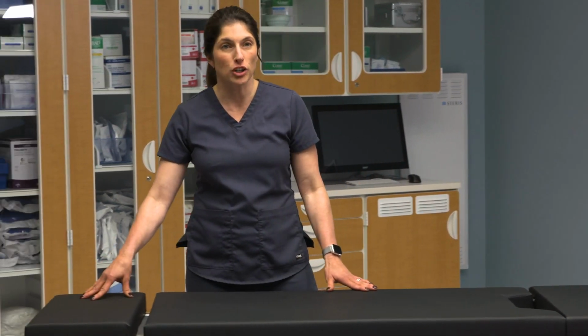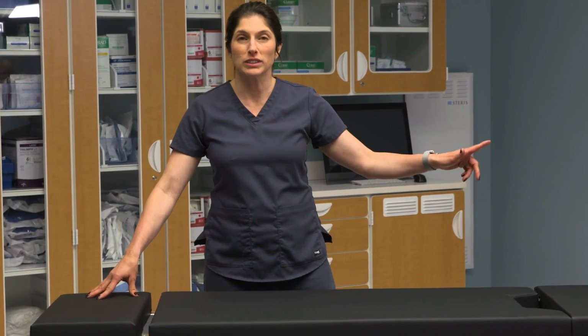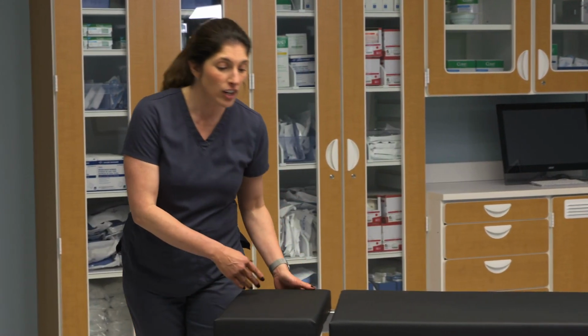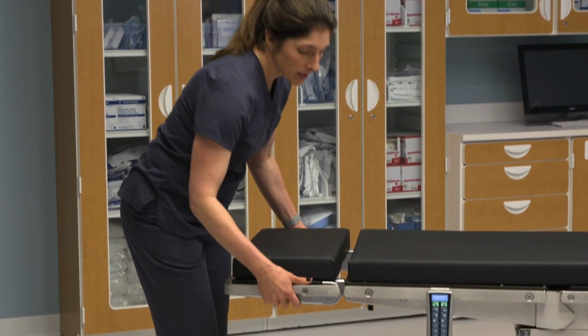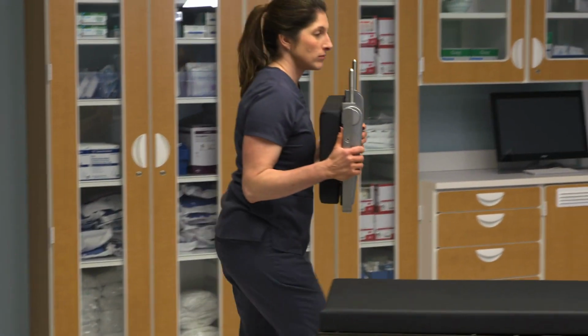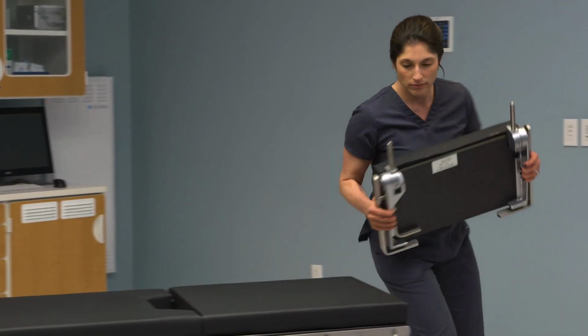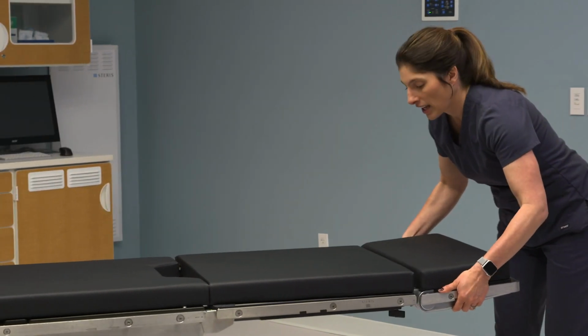So I know that one of the things you all love about your 3085 is that you can take the head section off and place it at the foot section when setting up for lithotomy procedures. The good news is you can still do that with the 4085. So you unscrew the locking knobs, pull the head section out, bring it to the foot, and lock it down in place. Now you've got a place for the patient's legs until you get them in lithotomy.